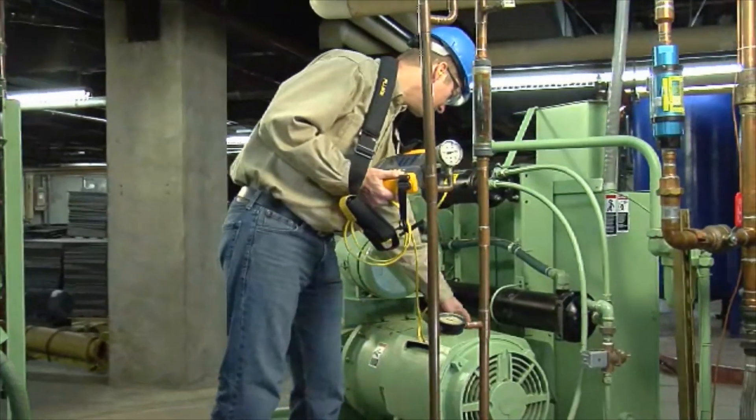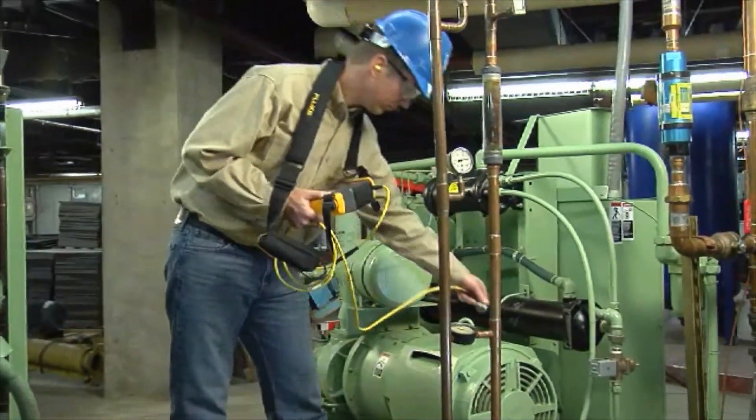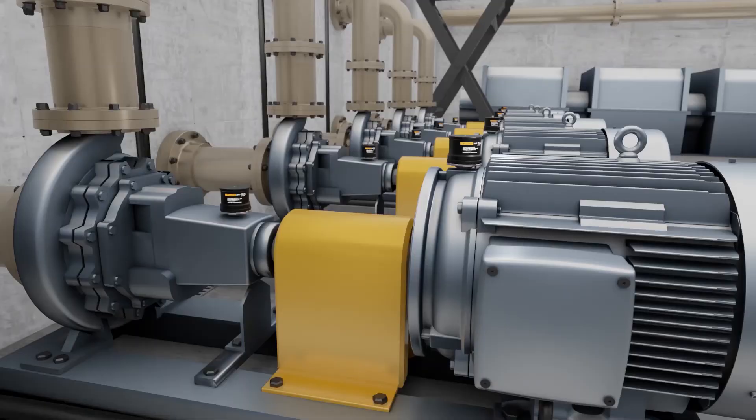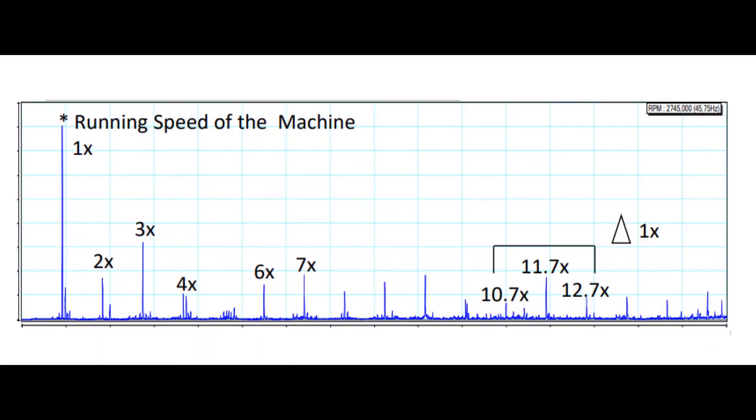If vibration is high, use a vibration portable analyzer or wireless analysis sensor to better understand the specific fault. The FFT, or fast Fourier transformation, removes random noise by looking only at repetitive signals.